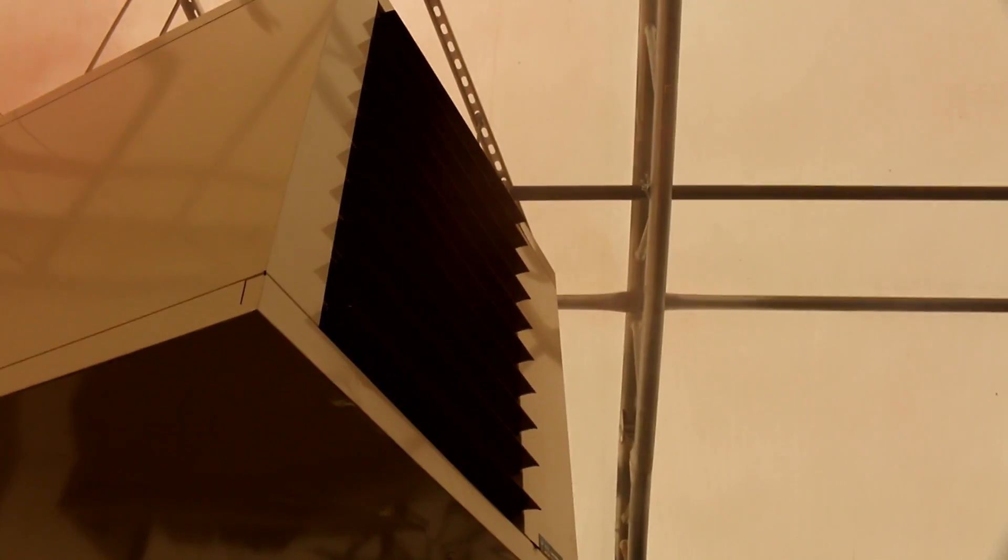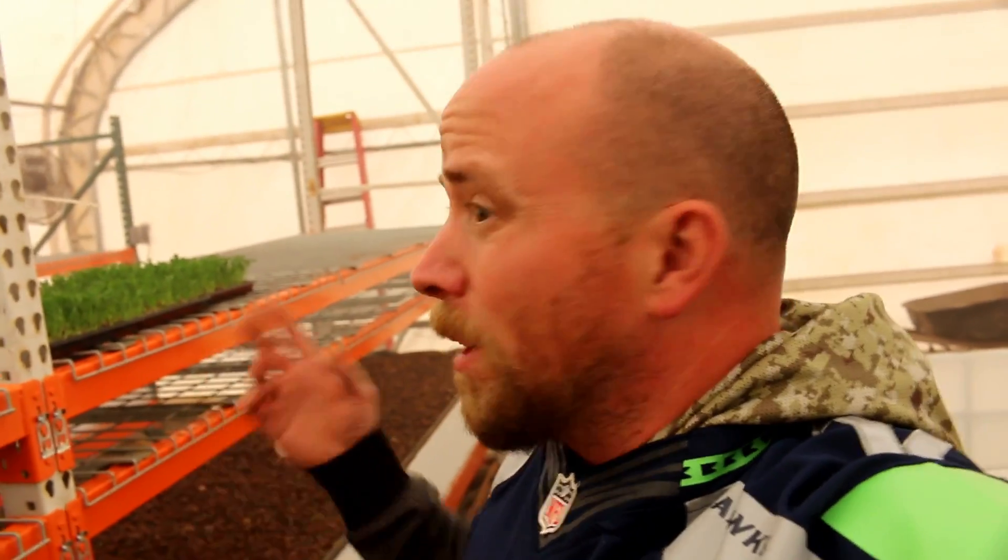The real good news is that the smoke — look at it come out there — it's kind of hard to see on camera but it is really getting tossed out. You can see some smokiness over there, it is blowing really really well off of the heater and it's distributing throughout the building really quickly, which is what we wanted to see. But I was really hoping to get some more of where the actual airflow currents are. What I'm taking away from this experiment is that the fans we have set up with the heater blower going definitely distribute the air in here really rapidly — it diffused so quickly. We might have good enough airflow, but those weren't really smoke grenades, they were reveal smoke bombs, which were absolutely horrible.